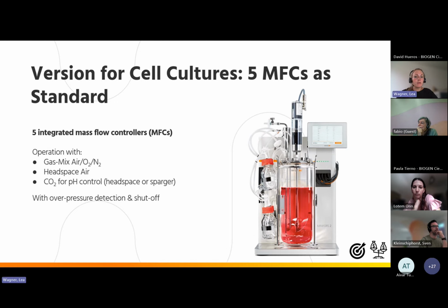Now to the gassing for cell cultures. So they have different needs. This is why they need more MFCs, so they need more different gases. So we have 5 MFCs in the cell culture version as a standard. There are MFCs for air, oxygen, and nitrogen for the gas mix, because you also need nitrogen to lower the oxygen concentration, because a too high oxygen concentration is toxic for cell culture. We have an additional MFC for headspace gassing to avoid foam formation.